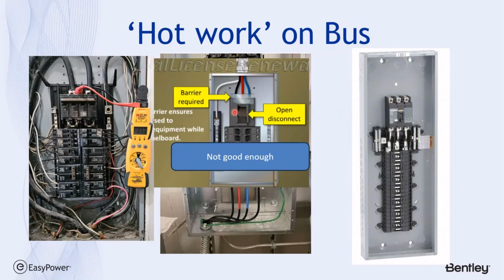Now, an argument could be made, well, most arc flashes are initiated by an inadvertent touching of the bus, so why doesn't this count? Well, it will count as far as reducing the frequency of arcing faults, but it doesn't protect once that fault's established. So take it upon yourself to make sure you're justifying using the main.